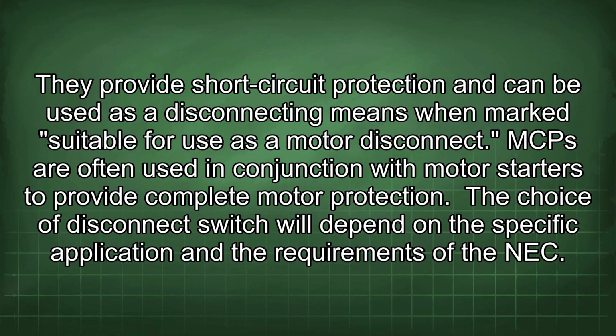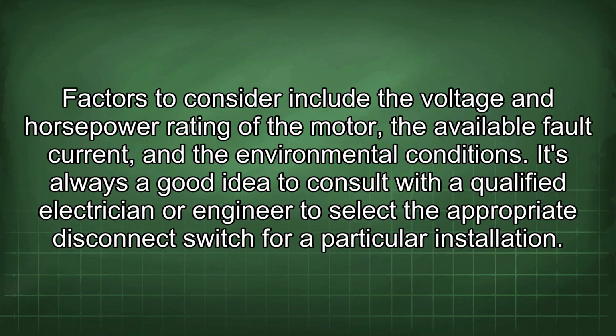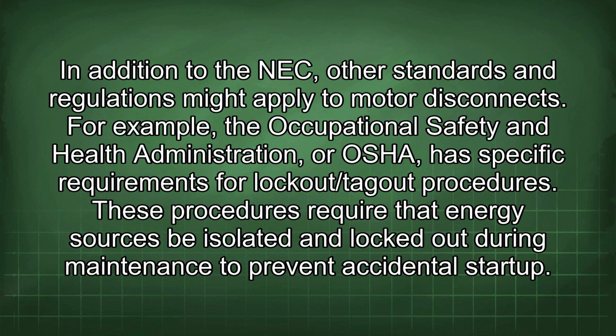The choice of disconnect switch will depend on the specific application and the requirements of the NEC. Factors to consider include the voltage and horsepower rating of the motor, the available fault current, and the environmental conditions. It's always a good idea to consult with a qualified electrician or engineer to select the appropriate disconnect switch for a particular installation. In addition to the NEC, other standards and regulations might apply to motor disconnects.